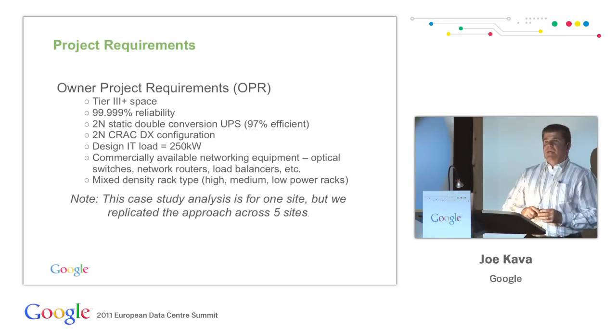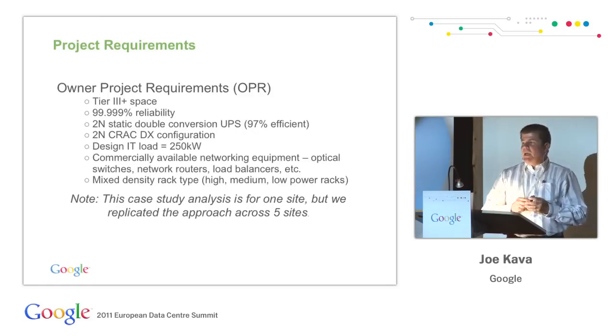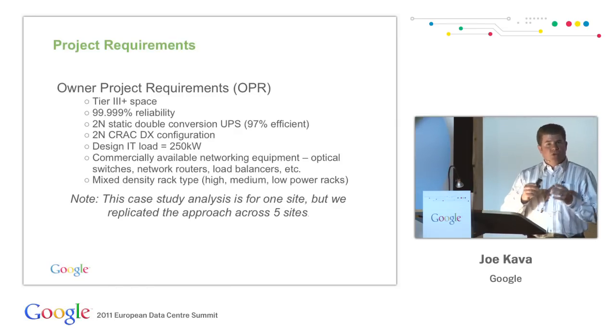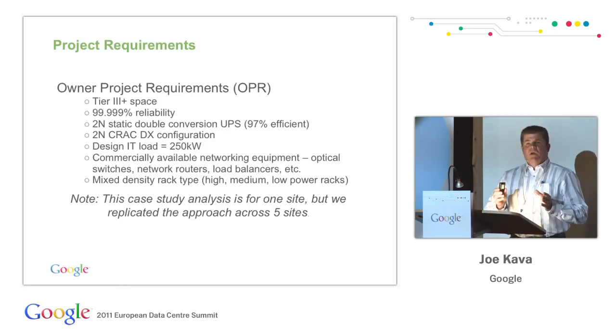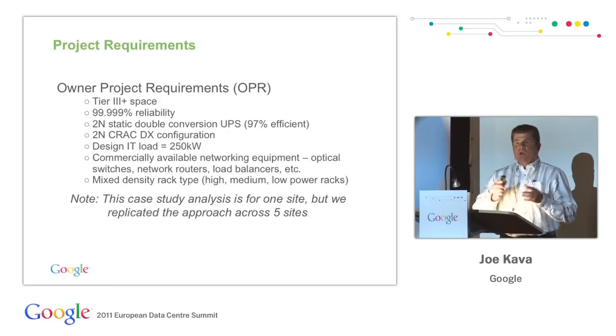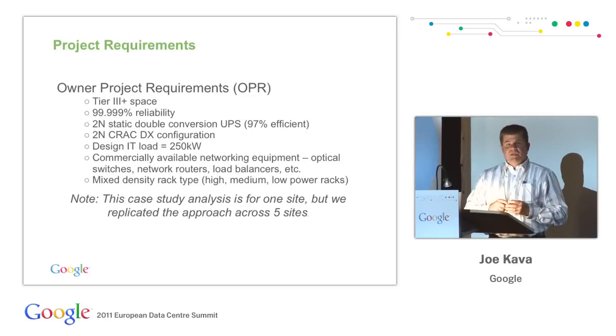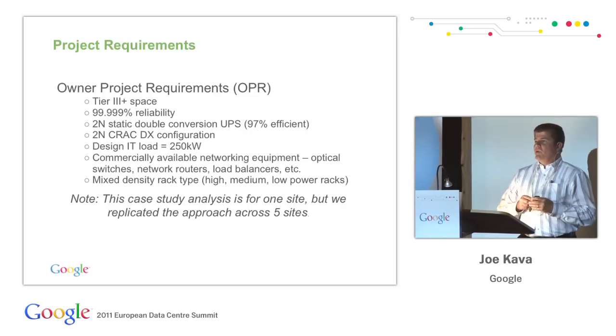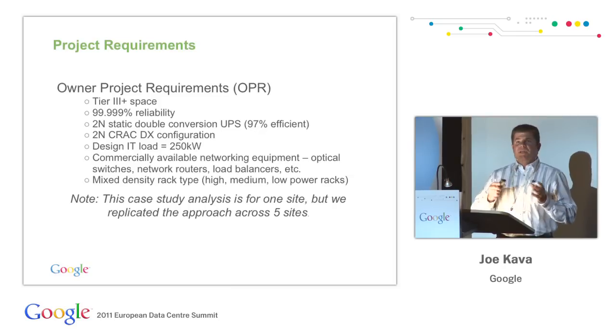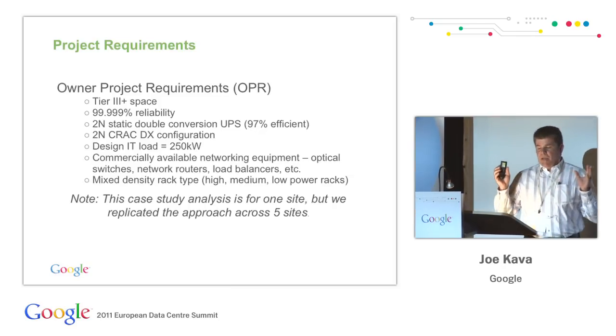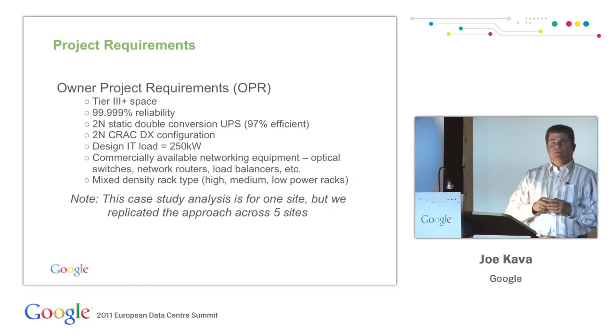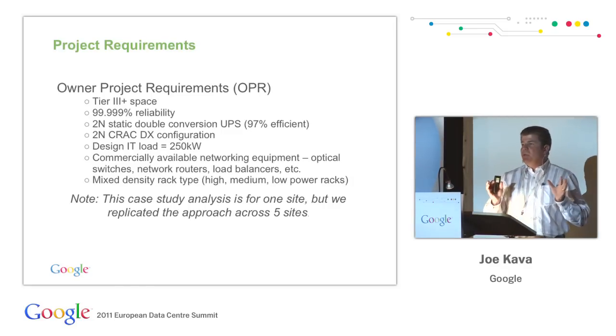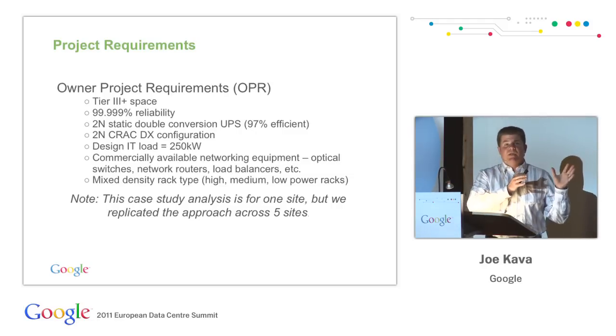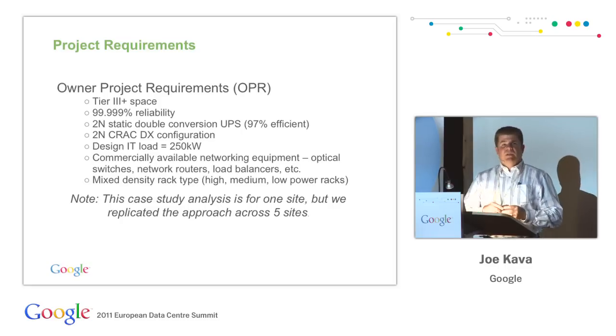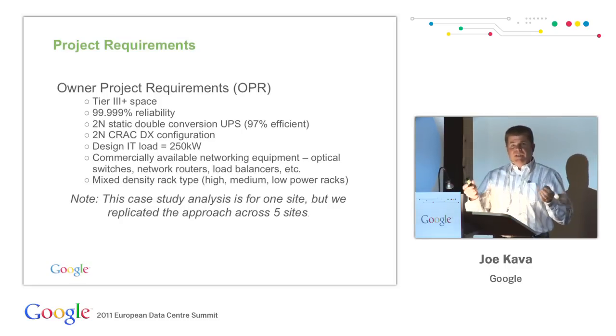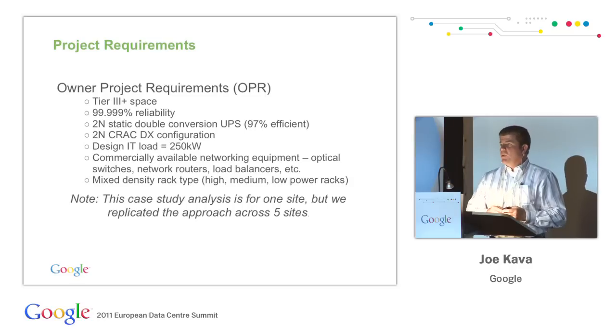At the beginning, I think like many of you, there's different business units, and different business units design their server rooms with different requirements. In this case, our requirements were to design for ultra-high reliability and availability. These were typical 2N UPS backed up power distribution systems, multiple redundant cooling systems. They were moderately sized, designed for about 250 kW of mixed IT deployments. So there was going to be some higher density equipment, some lower density equipment, all commercially available equipment. So these requirements really look like what I expect most of your data center requirements look like.